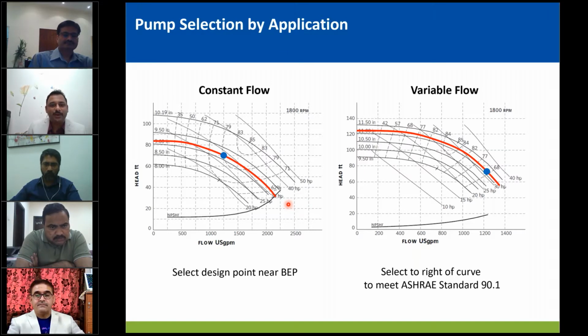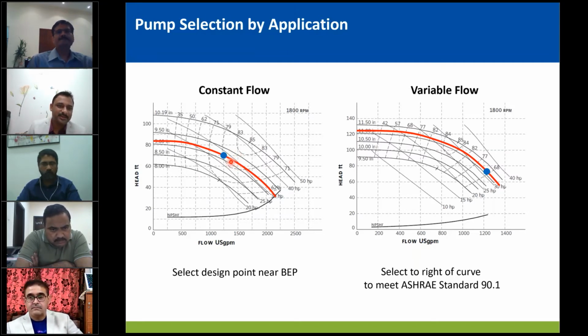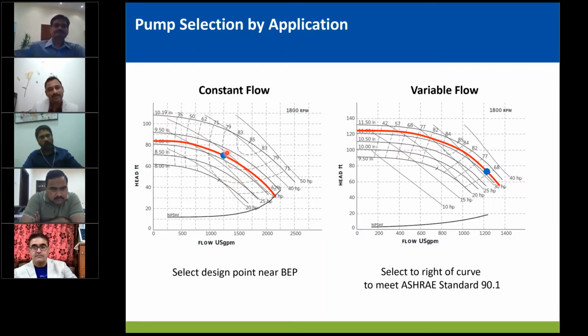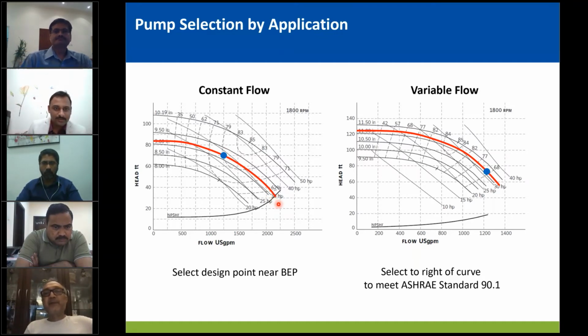Now you end up sizing with a 40 HP motor and a 40 HP starter panel for this. Whereas if you had a variable speed pump on this particular application, you could have selected a 30 HP motor, and you could have programmed it not to load the motor more than 30 HP. Now you don't need 1250 GPM as the design flow. You don't need more than probably 5% extra, but more than that is still a waste of energy, and it's not good for the heat transfer of the larger piece of equipment. Now, if you have a variable speed controller on that pump, even on a constant flow, it will still reduce the motor size and the starter panel size, and it will still result in a lower installation cost and energy savings.